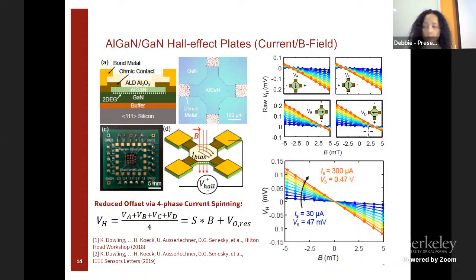Unfortunately, when you operate this in a zero magnetic field, you experience or observe something called offset. And this is something that occurs with a lot of sensors, meaning that in a zero magnetic field, you have a voltage that's present. And that's something you want to mitigate. And so we use something called current spinning, where we're averaging out the response as we apply current around these electrodes. And then using this equation here, we can create a zero crossing. So it's basically an averaging technique. So where at a zero B field, we now have a zero voltage.